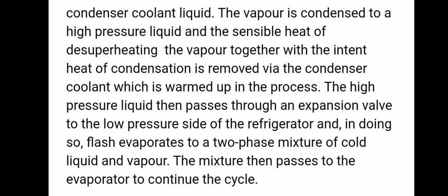The pressure of the vapor has been increased, and the vapor now has a temperature of condensation substantially greater than the temperature of the condenser coolant. The vapor is condensed to a high pressure liquid, and the sensible heat of desuperheating together with the latent heat of condensation is removed via the condenser coolant.